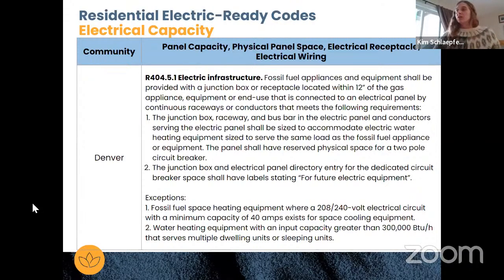Here's Denver's language, and they have that requirement for a 2-pole circuit breaker. However, I wanted to note that Denver only requires that for water heaters, and no other appliances. This section says: the junction box, raceway, bus bar, electric panel, and conductors serving the electric panel shall be sized to accommodate electric water heating equipment sized to serve the same load as a fossil fuel appliance or equipment. So that's how Denver set it up. This type of language could be used, taking out the specific acknowledgement to the electric water heater.